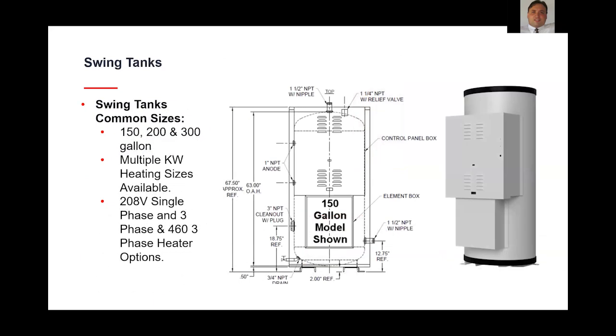Again, swing tank sizes are typically available in different increments from manufacturers. This is just an example of some of the ones that Mitsubishi offers, up to 300 gallons. You can see here with different voltages available. Again, this is going to vary by manufacturer. This isn't, as I mentioned, something that you specifically have to buy from the manufacturer. We're more concerned typically with that primary side and secondary side with the storage tank farms.